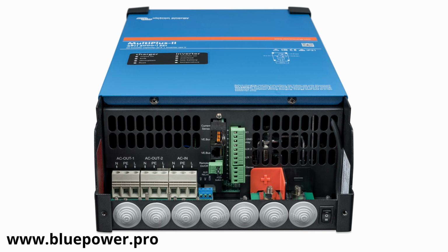And then next we've got our DC input connection on the right hand side of the unit. Over here we've also got our switch. So over there we can see we've got 2 positions. So that's one which is on, where the whole unit is switched on. So the inverter and the charger is powered. On switch position 2, only the charger is powered. So then the inverter will only charge your batteries, it won't supply any loads. So make sure that your inverter is also switched onto the correct position.